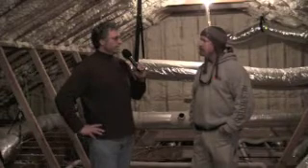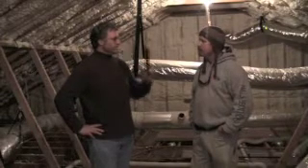And what SEER are these units? These are 16 SEER 2-stage. So 16 SEER, that would be a high efficiency unit? It is, yes. It's high efficiency with what people are becoming more familiar with called variable speed blower motors. So we can adjust airflow for noise, another indoor air quality issue, if we need more capacity somewhere. And then it's good for varying for dehumidification. If your unit has dehumidification capabilities, it can speed up and slow down the fan to help dehumidify better.